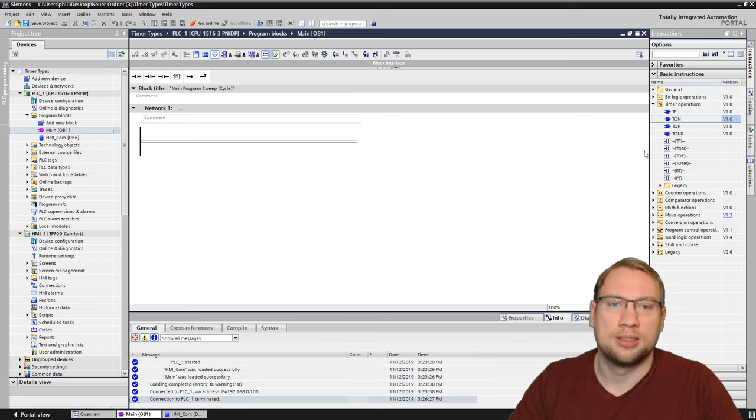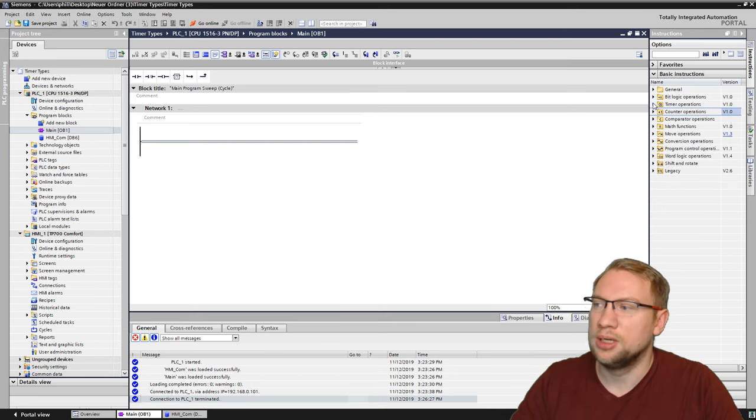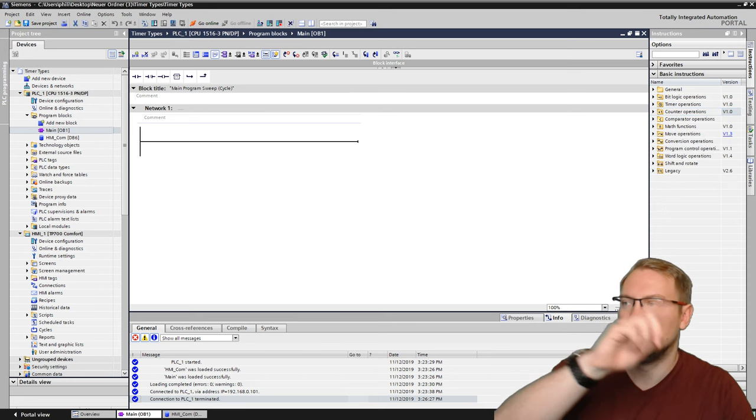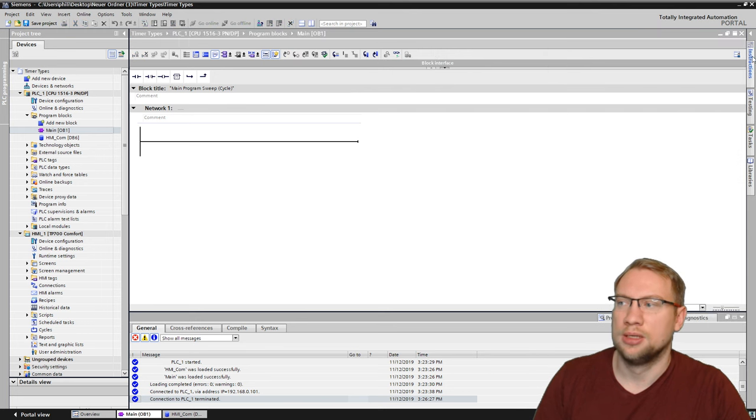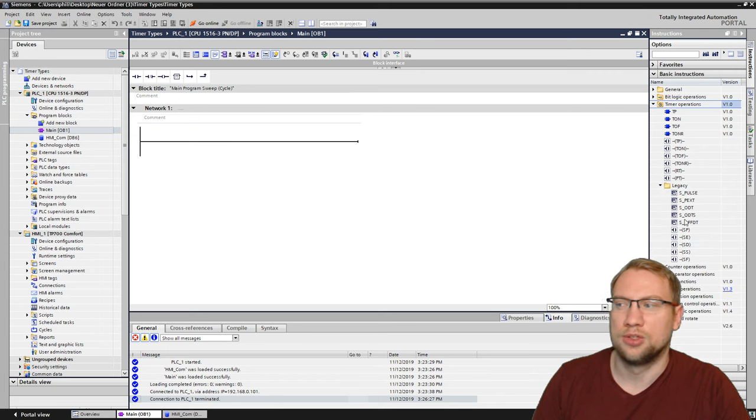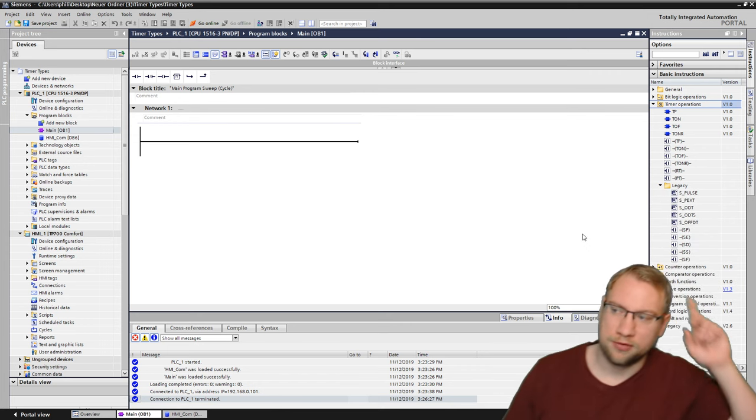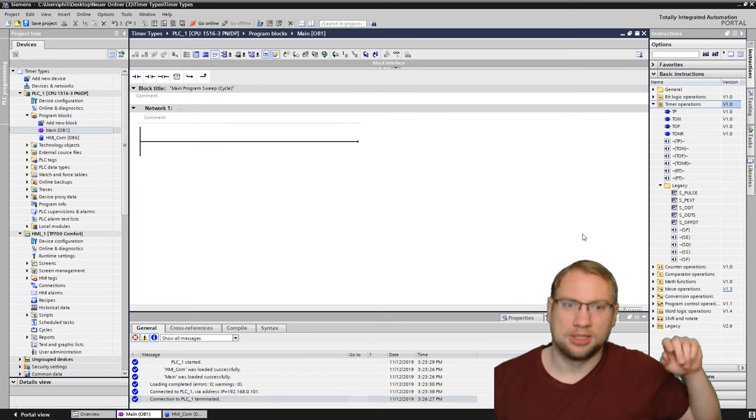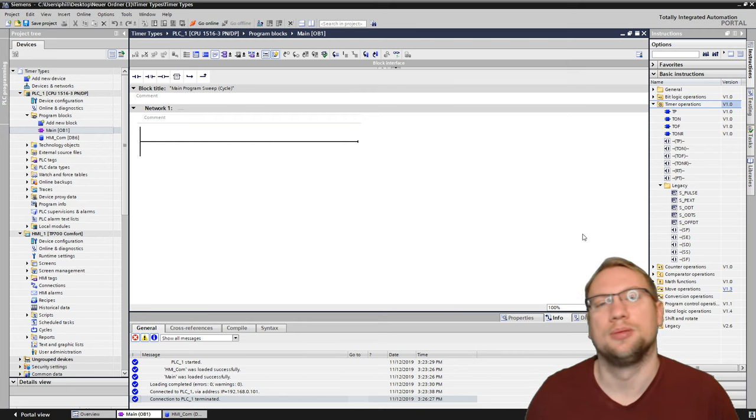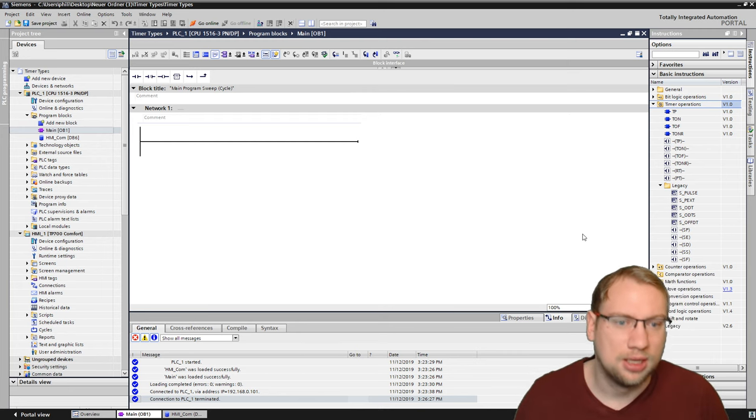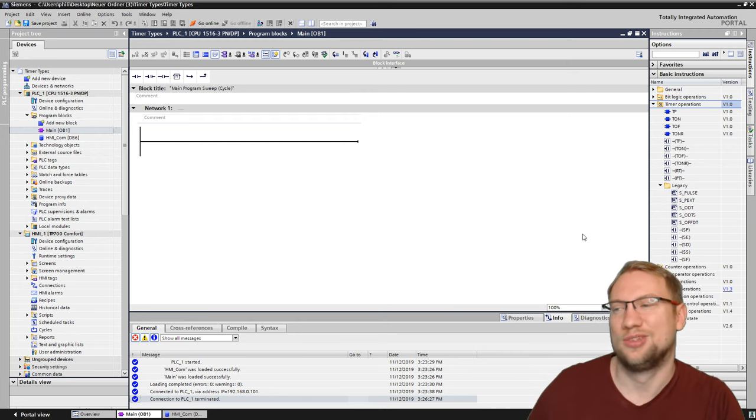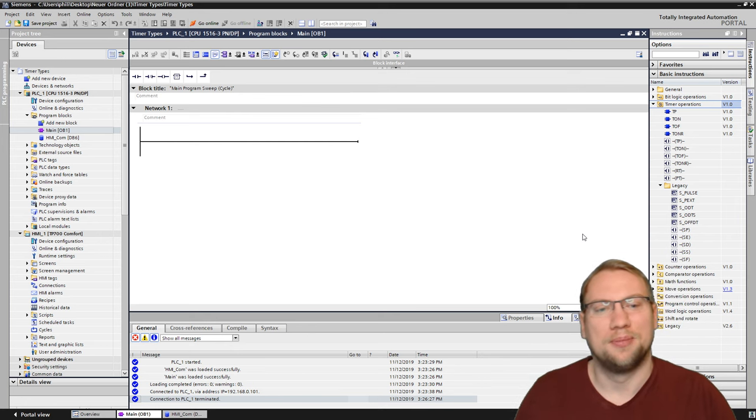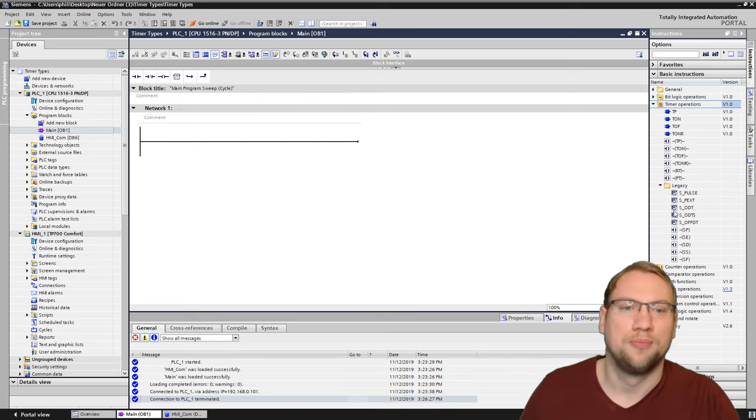I want an on delay. The timer in general, you find in your instruction window on the right. Instructions, and there we have timer operations. You see there's some more, and there's also those legacy ones. I will also make a video about those, but the legacy ones you should actually not use anymore. Those are S5 timers, prehistoric, like 20, 30 years ago.